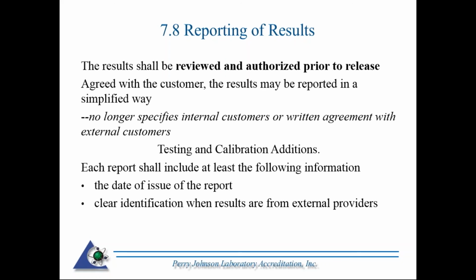A couple things for both testing and calibration. Some additions are the date of issue of the report. So that is actually when the report is generated. If it happens to be the same day that the calibration or testing was performed, then it needs to be reported as the same date. If the report is generated 2 or 3 days after the test or calibration activities were performed, then that date needs to be recorded. And it has to be a clear indication when results are from external providers, i.e. subcontractors.